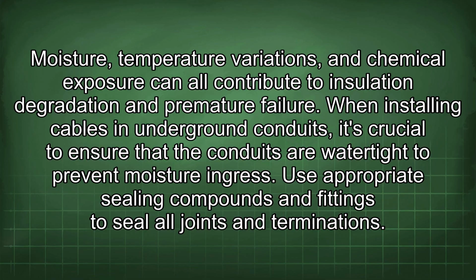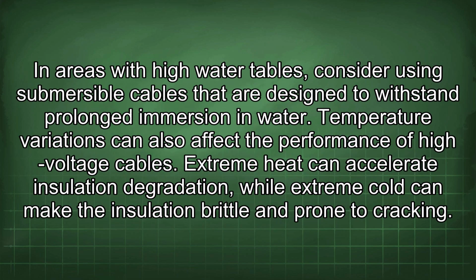When installing cables in underground conduits, it's crucial to ensure that the conduits are watertight to prevent moisture ingress. Use appropriate sealing compounds and fittings to seal all joints and terminations. In areas with high water tables, consider using submersible cables that are designed to withstand prolonged immersion in water.